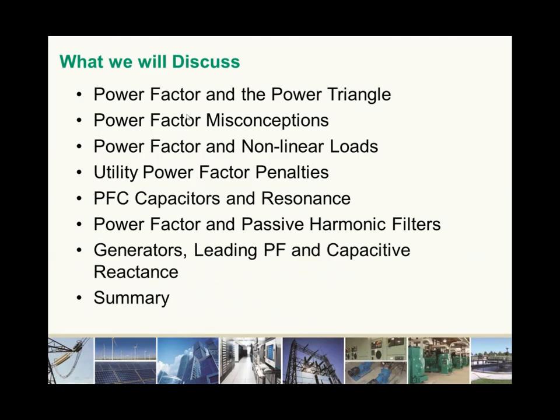Today we'll be discussing power factor and the power triangle, the 6 power factor misconceptions, how the harmonics generated by nonlinear loads affect power factor, utilities' power factor penalties, power factor correction capacitors and the potential for resonance with the power system, how passive harmonic filters can improve power factor, and the effect of leading power factor and capacitive reactance on generators.